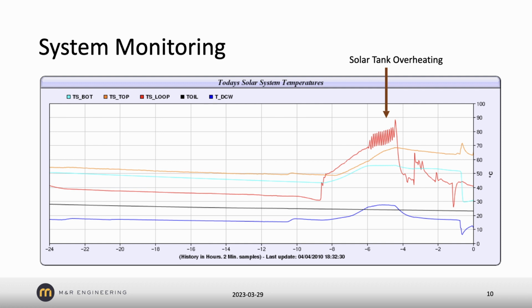One thing you can see here is this red line going left to right over a 24-hour period. This is the solar tank, or actually the glycol loop running up to the solar panels. You can see the loop temperature cycling up and down rapidly in the afternoon, because the system had peaked in temperature. This was even in April of my first year.